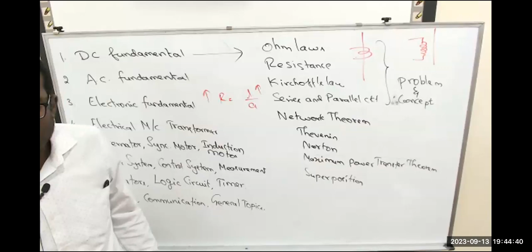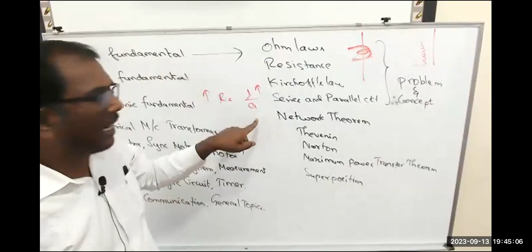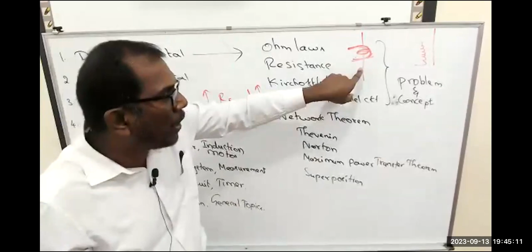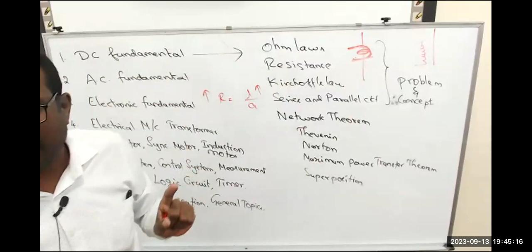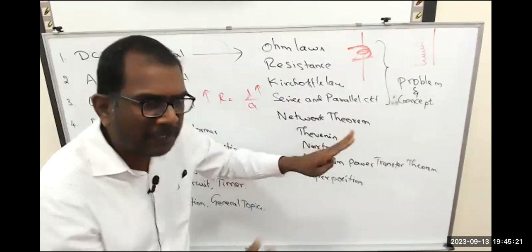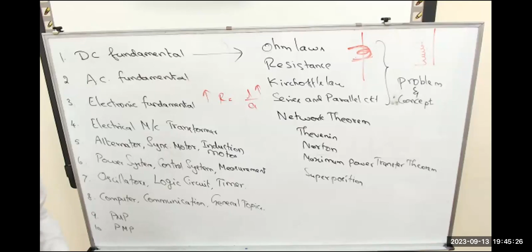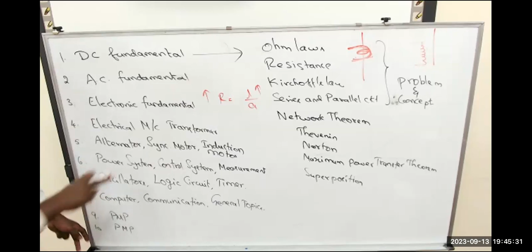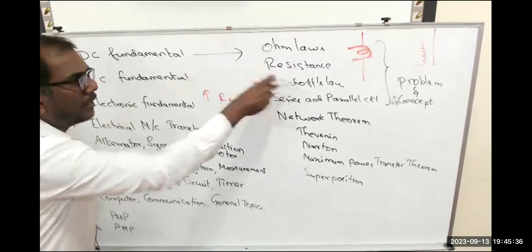And other things. Usually in CT we use thick wire, and here we use thin wire. Thick wire has a high cross-sectional area, so resistance is low. So there is a specific reason why we use thick wire and only 1 turn, based on the resistance. R is equal to rho L by A formula. That's why this concept is very useful. CT, PT is related to measurements. Or if you go to the alternator, we have stator winding, field windings, exciter winding. The windings are also related to this. So that's why it's basics, but it's applied to all of these.